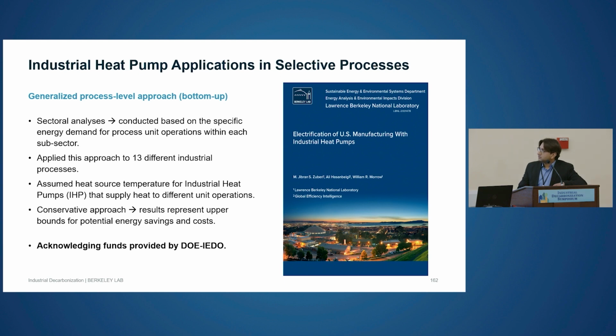And one thing I would like to mention is that it's a conservative study. When I say conservative, I mean that the heat source for these heat pumps was assumed as ambient. We didn't look into the waste heat resources that are available from these facilities, because waste heat is very site specific and the amounts could vary substantially. So it was very difficult to generalize those cost curves, composite curves for applying the pinch techniques and see how the COP varies. But that is something that could be done in the form of case studies once we start applying it for the individual facilities.